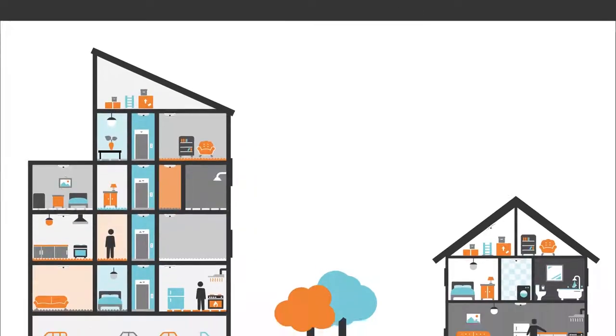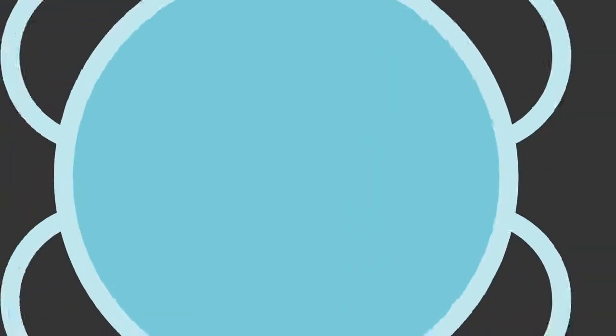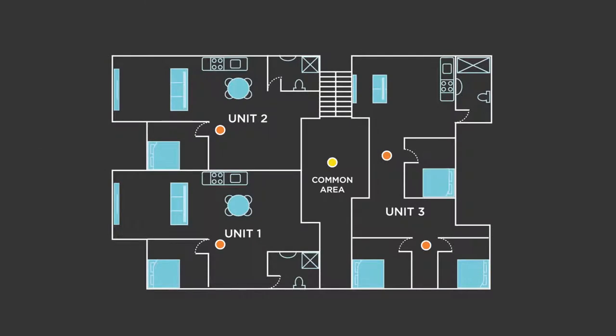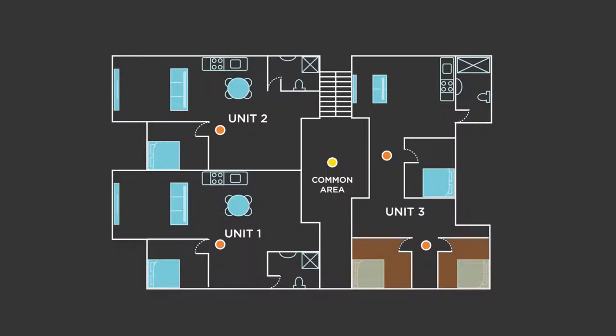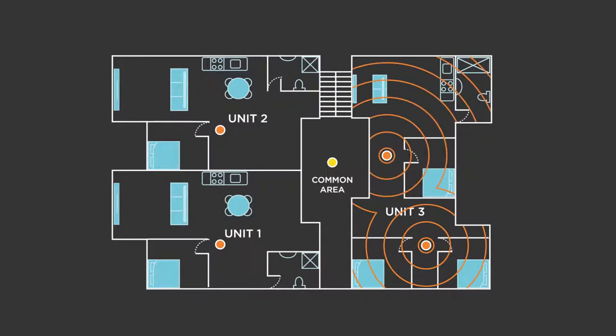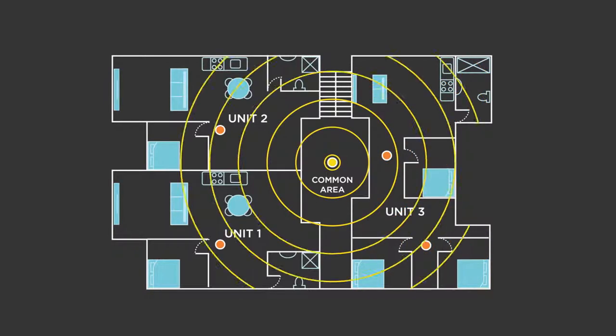These include one, know your system. First, let's identify what is currently required by the National Construction Code. Within a house or apartment, smoke alarms are required on or near the ceiling in any storey containing bedrooms. Where bedrooms are separated from the living area, this may require more than one. Where there is more than one alarm installed per dwelling, the smoke detection system must be interconnected and be installed in apartment building common areas, except where the building is sprinkled, and be connected to activate a building occupant warning system.